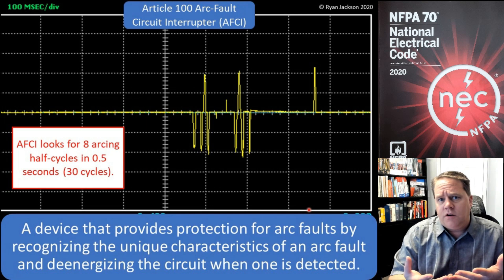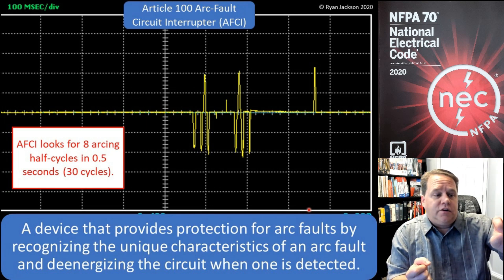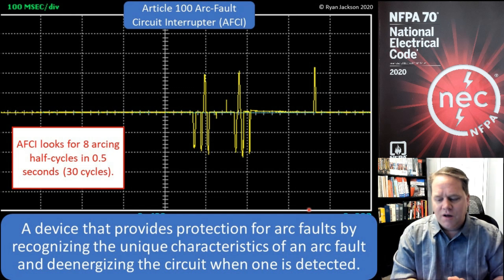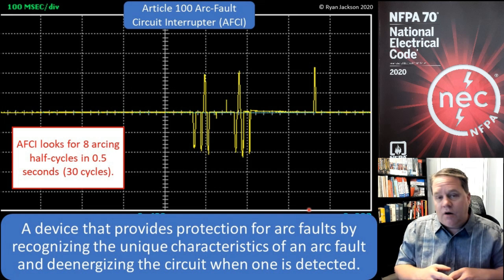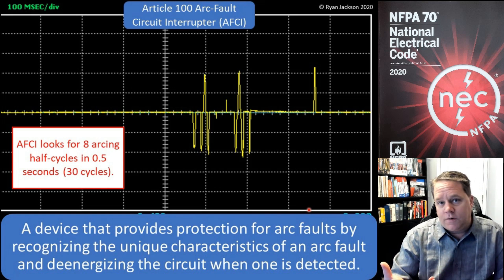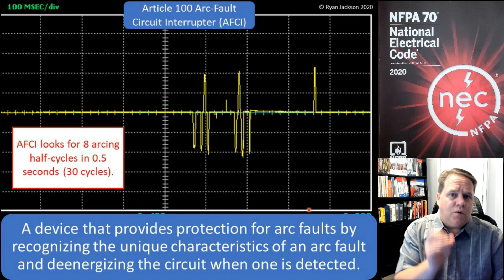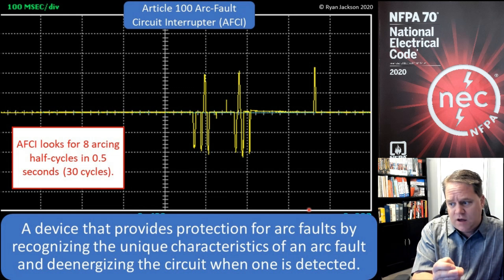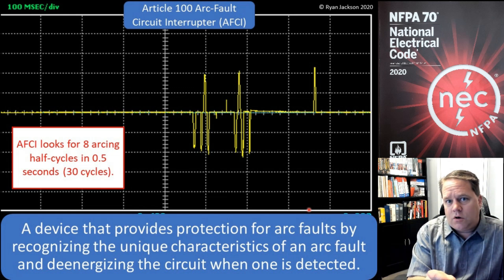You've probably turned on a light switch in the dark and seen a little blue pop behind the wall plate — tiny and it's gone. That's a series arc, and it's not a dangerous event, so we don't want an arc fault breaker to trip every time that happens. We do have to recognize what an arc is and when it's dangerous.